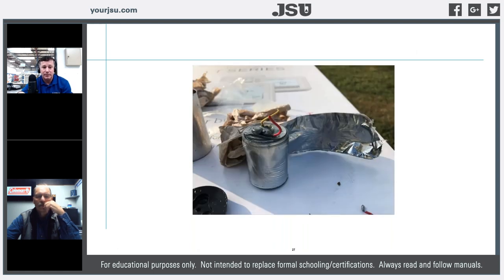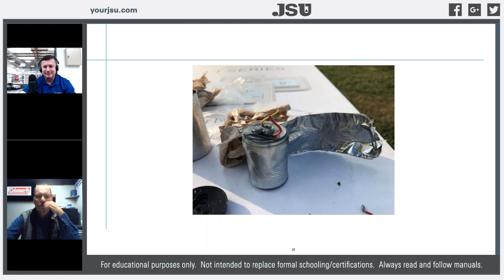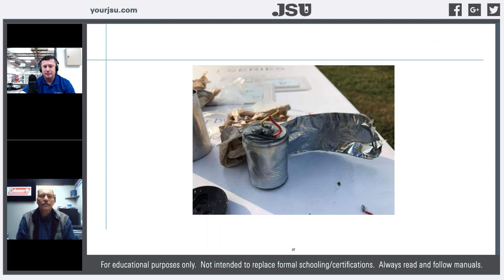When we look at the end of the roll on this OEM capacitor, there's a lot of winding on there, with contact points at the bottom where the common connects. For a 440-volt capacitor, the film should be made much thicker than a 370-volt. In this case, it might have been on the low side of film thickness for that voltage rating — which contributed to the failure.